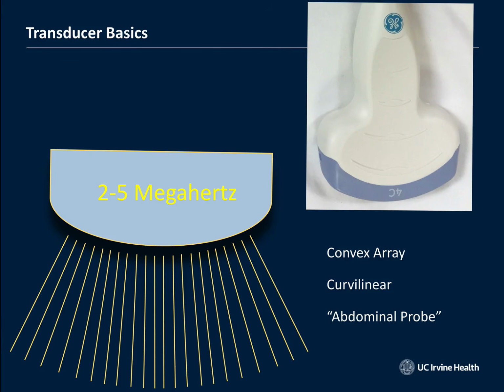Now, the different transducers do have different footprints. I just want to point out some basic components of that. So a large footprint, what we call curvilinear probe, or sometimes called a convex array. You hear it called a curved probe or abdominal probe. This one's got all these elements lined up in a sequential array, and the ultrasound beams fire into the body and then reflect back. But as you can see, right down the center of this probe, these beam lines are a little closer together. So on the edges of this convex array, I'm going to lose a little bit of lateral resolution, or the ability to tell that one dot are actually two dots side by side from one another.